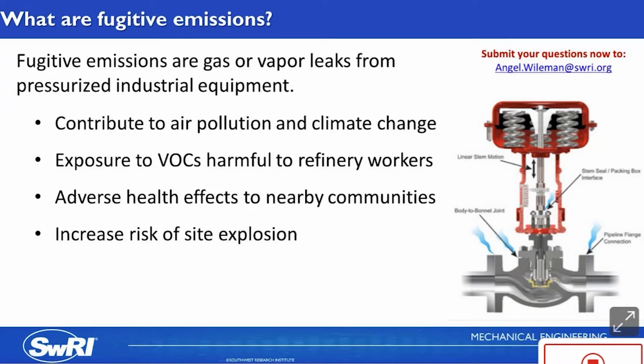And typically, these are sealed with a packing in the bonnet, but that packing will wear over time at extreme pressures and temperatures. There's also thermal expansion and contraction due to fluctuations in temperature that can increase leakage. Additionally, movement of the stem allows foreign particles and debris to move into the packing area, which can impact the wear rate on the packing as well as the ability to seal.